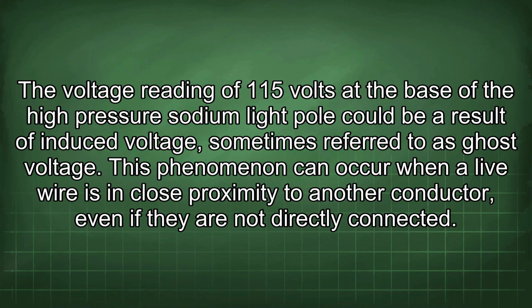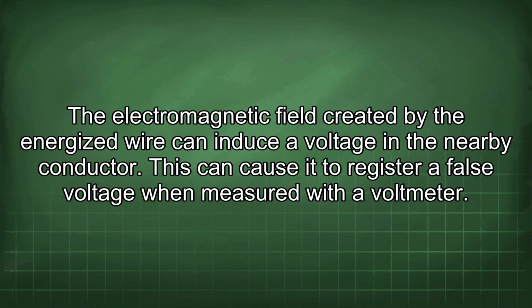The voltage reading of 115 volts at the base of the high-pressure sodium light pole could be a result of induced voltage, sometimes referred to as ghost voltage. This phenomenon can occur when a live wire is in close proximity to another conductor, even if they are not directly connected. The electromagnetic field created by the energized wire can induce a voltage in the nearby conductor. This can cause it to register a false voltage when measured with a voltmeter.